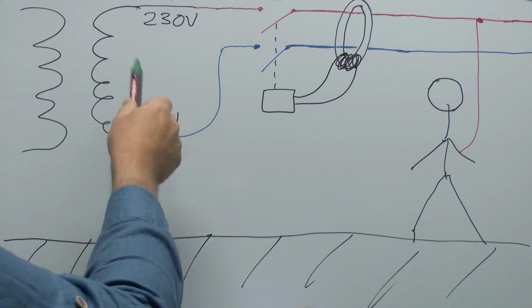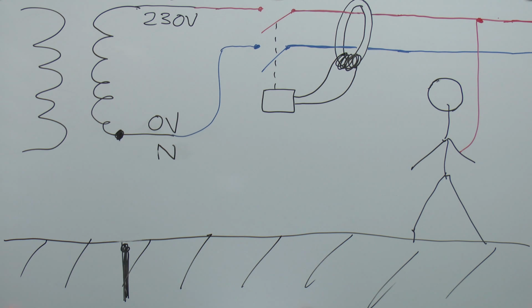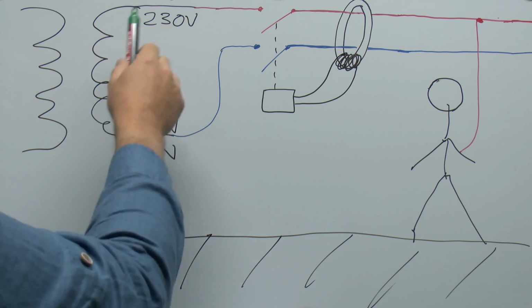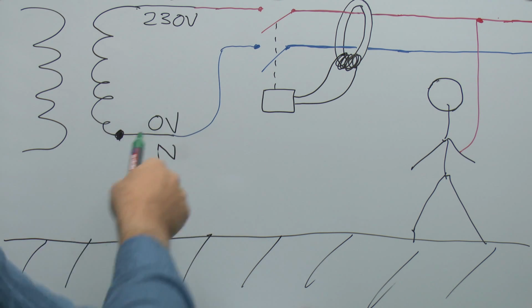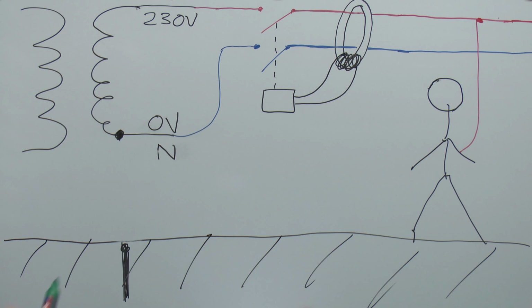And a similar thing can also be done just by using an isolating transformer, which may be used for various testing procedures. And a lot of small generators generally don't have the conductors referenced to earth for this reason. They're generally intended to supply, say, a single piece of equipment, and in that circumstance it's actually safer just to have a floating or isolated supply and not have it referenced to ground, which obviously avoids any kind of problems here.